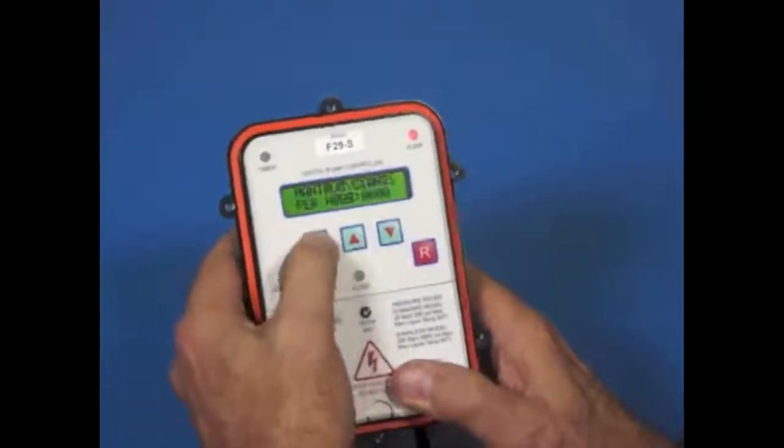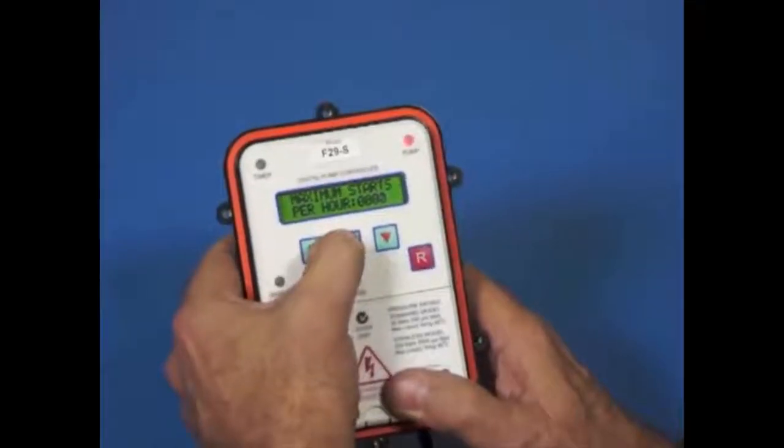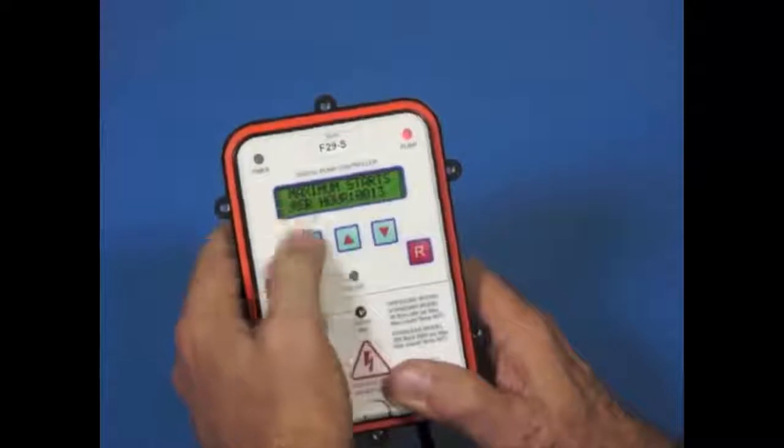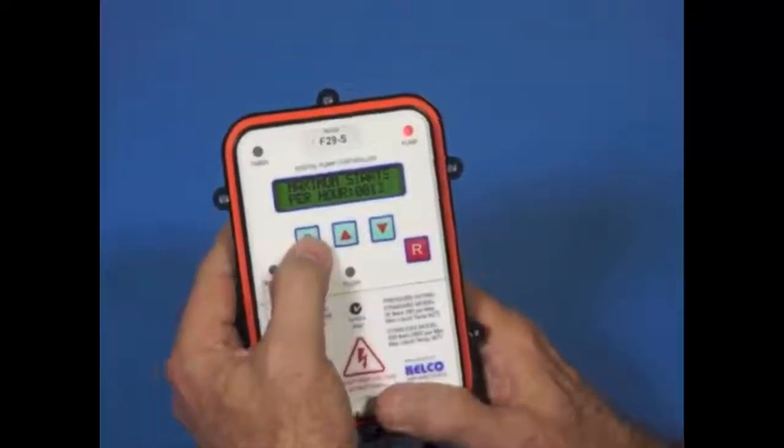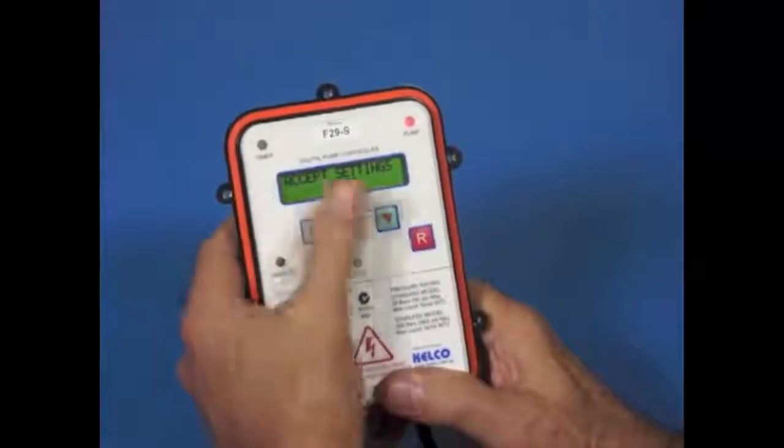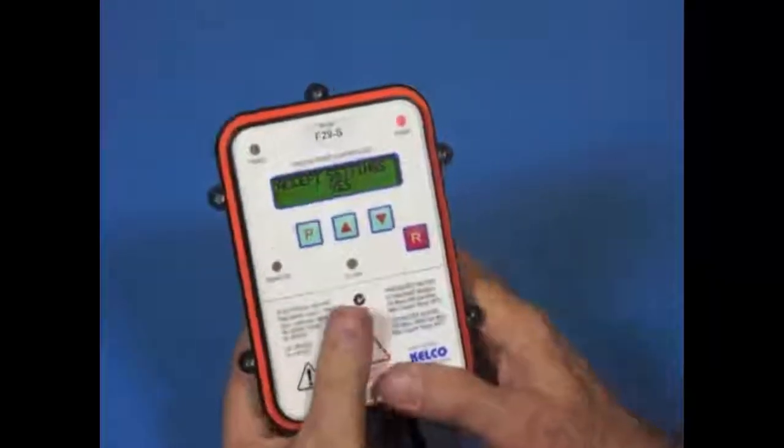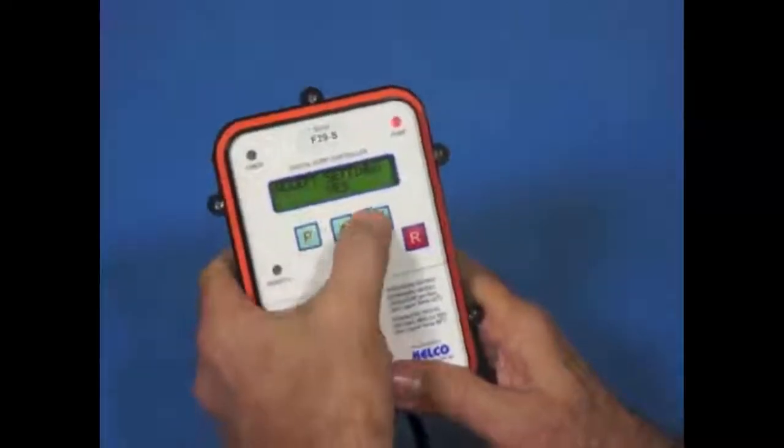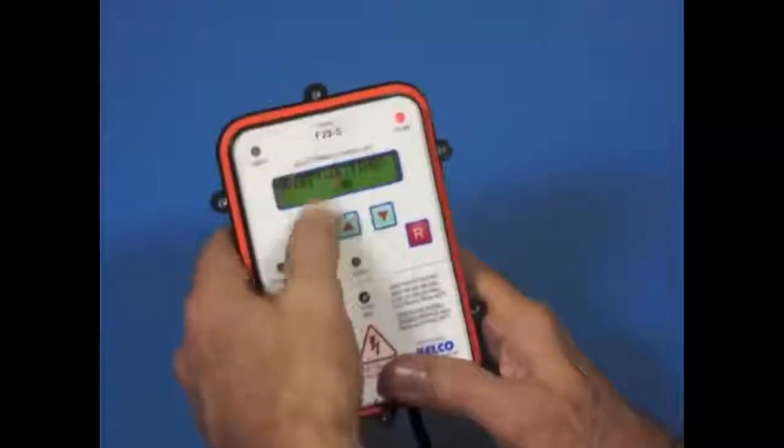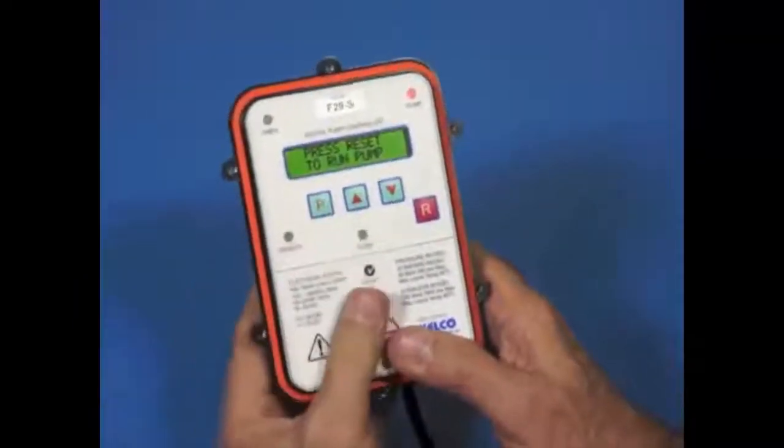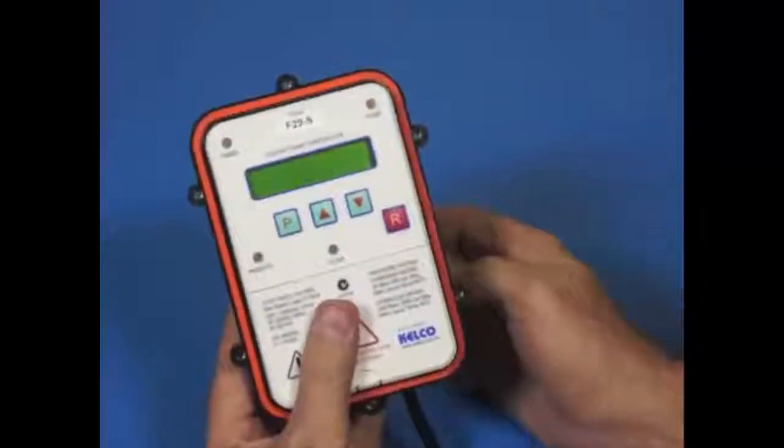Anti-cycling. Anti-cycling lets us set the number of starts per hour. We can set any value we like in there for starts per hour. And if that start rate is exceeded more than 10 consecutive times, the F29 will shut the pump down and display a message that the anti-cycling alarm has been triggered. Accept the settings, yes or no. If we select no to that, it'll take us back to the top of the menu and let us step through again. So if we press P to yes to accept it and then press reset to run the pump.